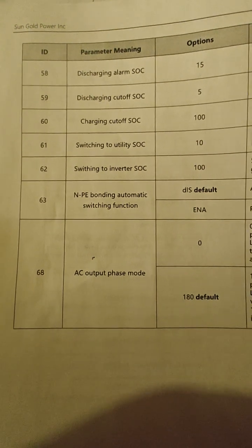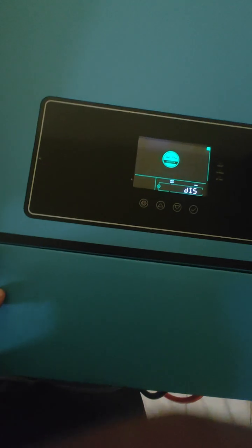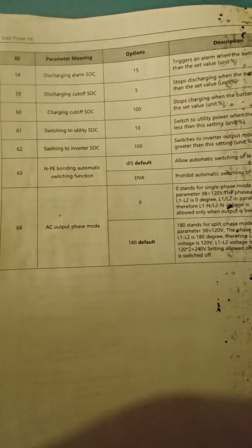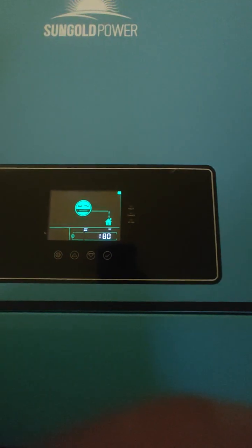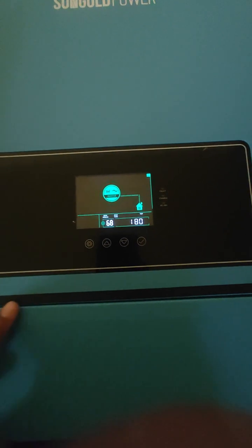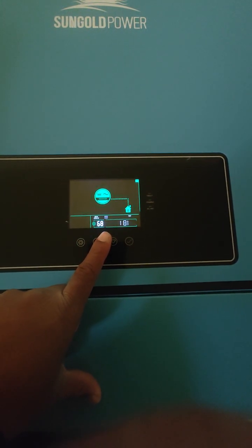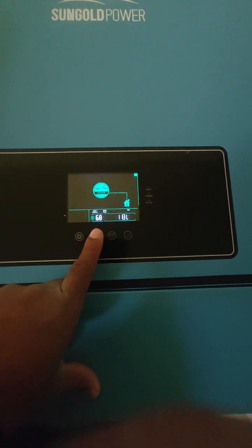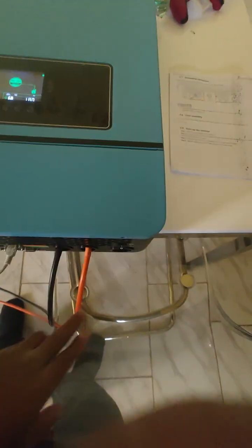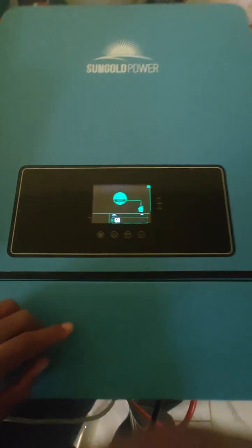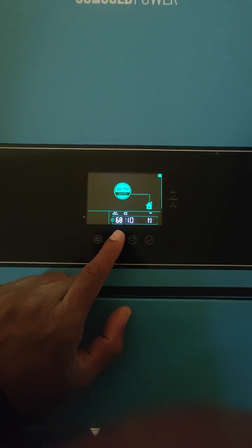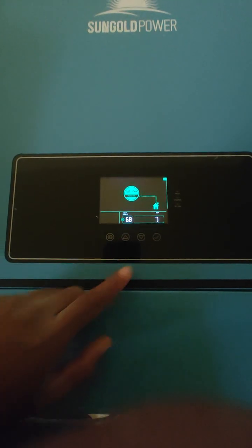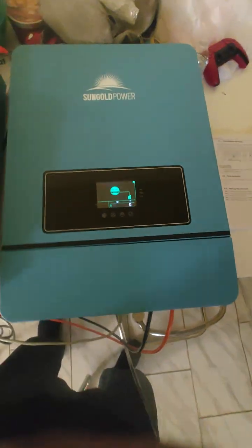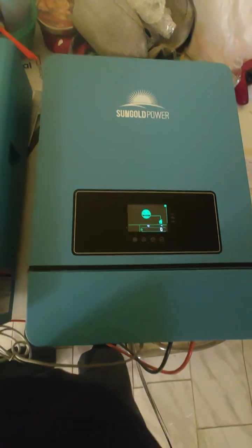NPE, bonding automatic switching function. What is that? Neutral bonding. Let's see what that is set to. That's set to disable, which is fine. The AC output phase mode. 180 is for split phase, so we'll change this to 0 for single phase. Oh, you can't change this unless your inverter is in standby. So change this to 0. That's it. Yeah, this completes all the settings.